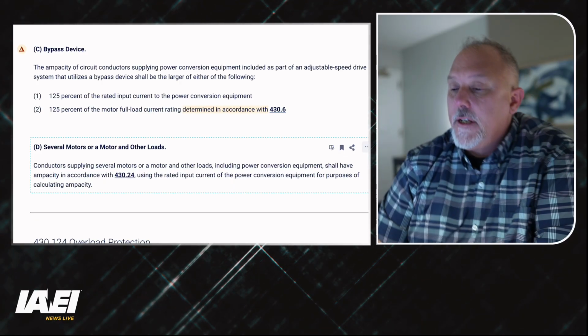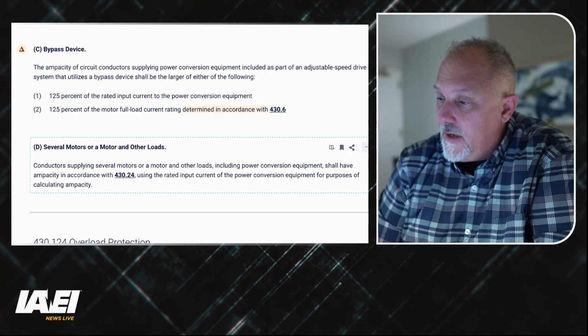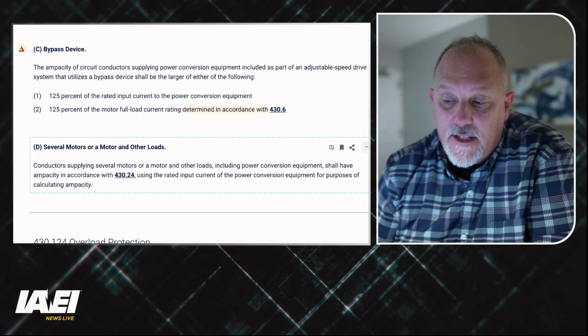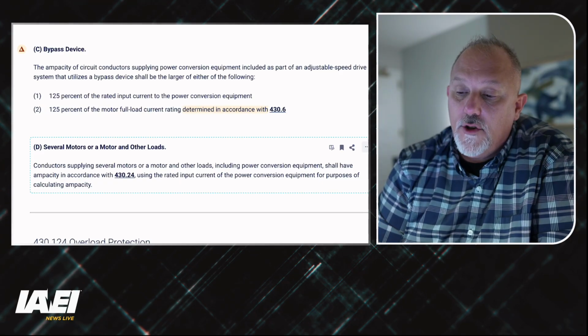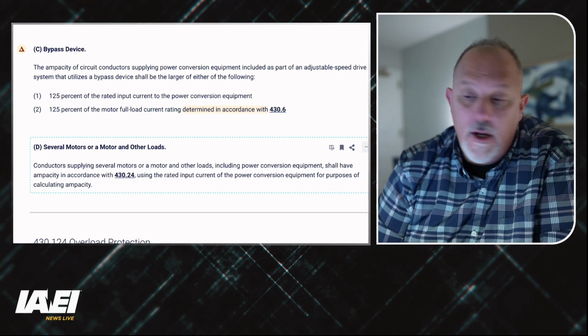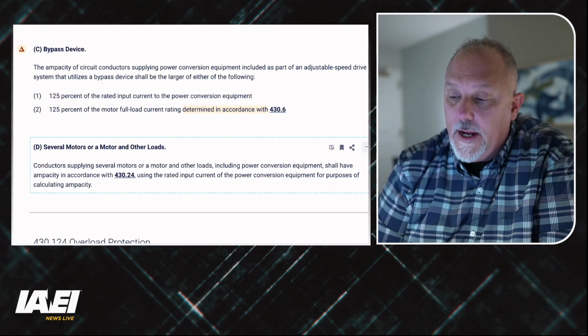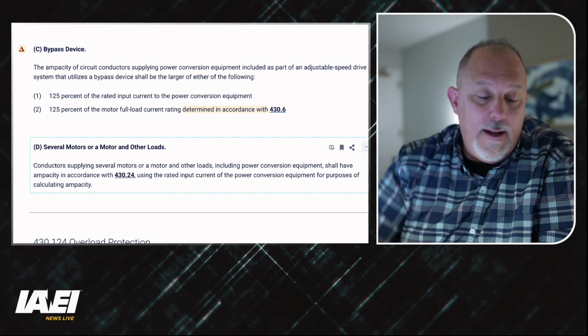And it tells you the ampacity of circuit conductors supplying power conversion equipment included as part of an adjustable speed drive system that utilizes a bypass device shall be the larger of either of the following: 125% of the rated input current to the power conversion equipment, or 125% of the motor full load current rating as determined in accordance with 430.6. And that makes sense because you have to make sure whichever one of those is larger, you want the ampacity of the conductor, because if you're in bypass mode and you're starting that motor across the line, you need to be able to handle the motor. And the drive may have a lower current rating than the motor does.